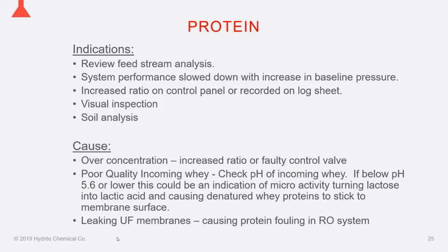Another thing that can cause protein to become more of a problem is if it is denatured, and this can be a result of pH or entrained air cavitation, basically creating the perfect storm of conditions, a very sticky, gummy complex with lactic acid that might also be in the feed stream. Either way, targeting the protein soil is going to be the best way to remove this.